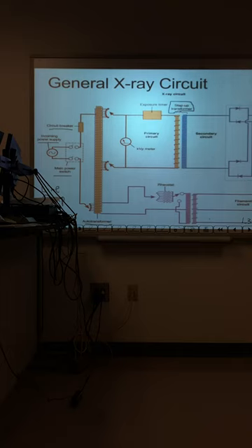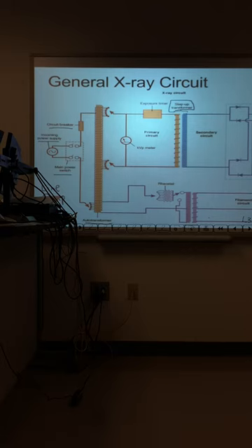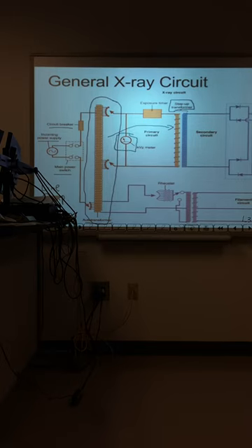The step-up transformer is used to increase the voltage from the auto transformer to the kVp, or kilovoltage, necessary for X-ray production. So this step-up helps make sure what we set on the console is going from here to here properly. You have this kVp meter here, reading out what we set at the console. It's working this way and then back this way to make sure that the output is proper for the X-ray production.